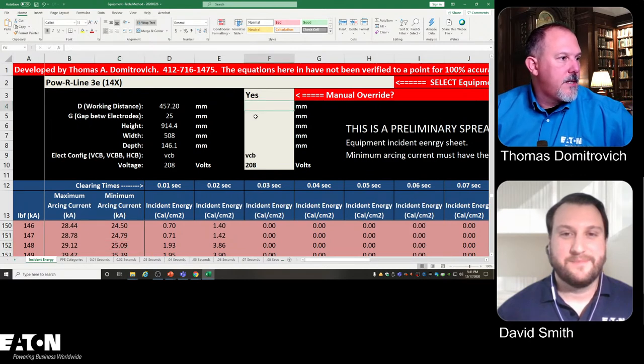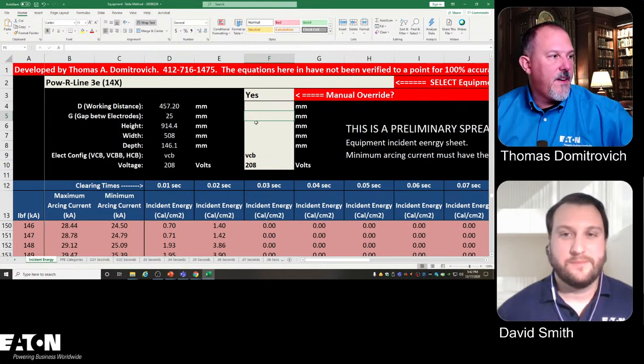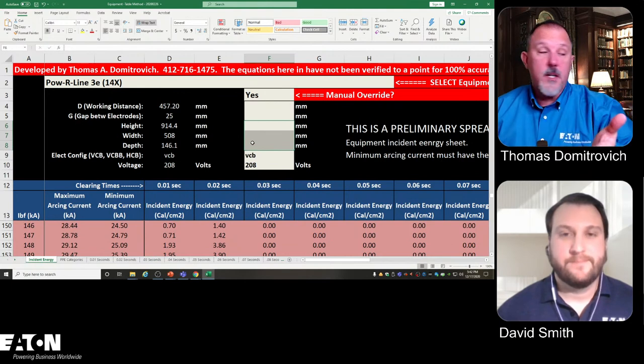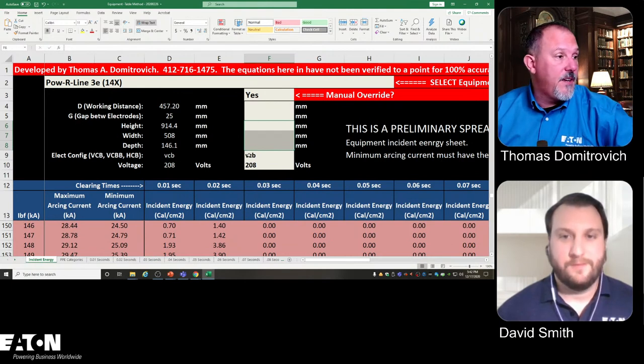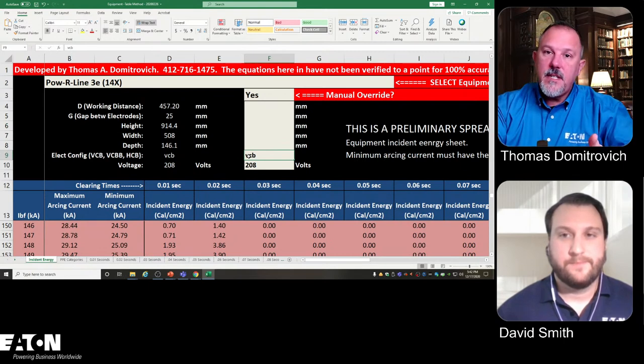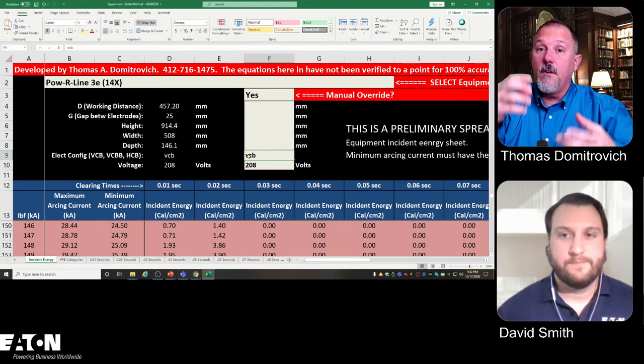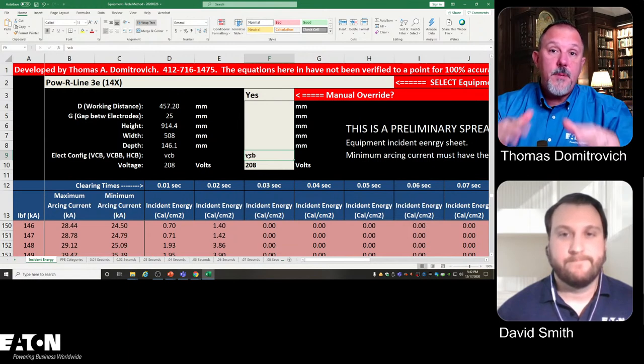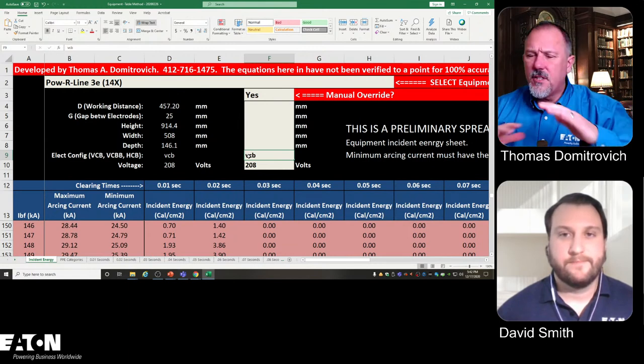I've got my working distance, that's my 18 inches. I got my 25 millimeter gap in the electrodes. I have the size of the enclosure, because we said the size of the enclosure makes a big difference. I've got VCB, and there are other configurations: VCB, VCBB for vertical with barrier, HCB for horizontal, and then there's stuff for air.